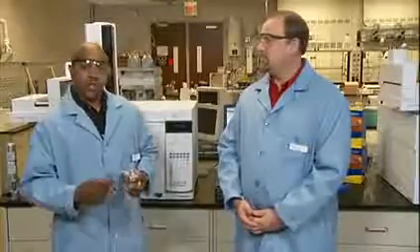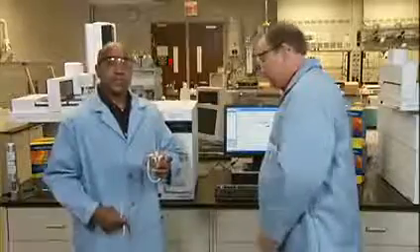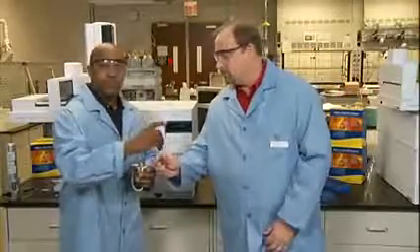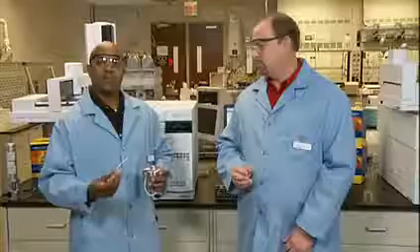First, you would have to prepare the inlet by removing the column from the bottom, the inlet consumables from the top, and disconnect the split line over here. Then you would take a long Q-tip soaked in solvent. If you're using hexane to clean the syringe, hexane should work. Then you would run a long Q-tip along the sides of the weldment to remove any contaminants.